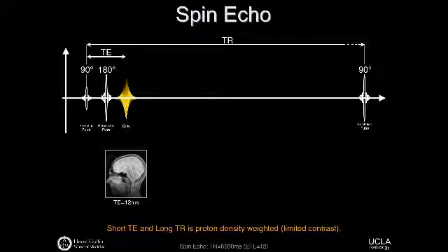And what we learned about with the spin echo sequence was there were a couple of things that we could control with regards to the timing. We can control the TE, and the TE is really related to T2 decay. And we can control the TR, and the TR is really related to T1 relaxation. In this simple sequence, we play a 90, we play a 180, we record the echo, and one echo gives us only part of our image, so we actually need to get hundreds of echoes to form the whole image. We'll talk about that later today. But after we have repeated this same experiment maybe hundreds of times, hundreds of TRs, then we have enough imaging information to build up this image here.